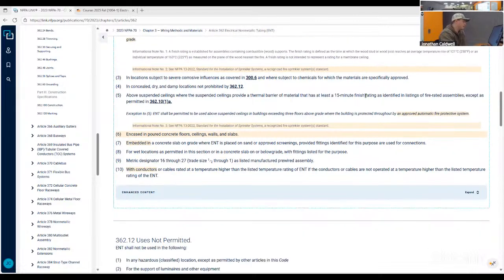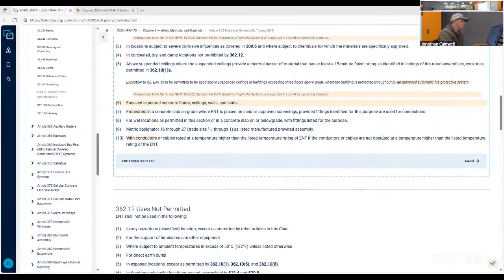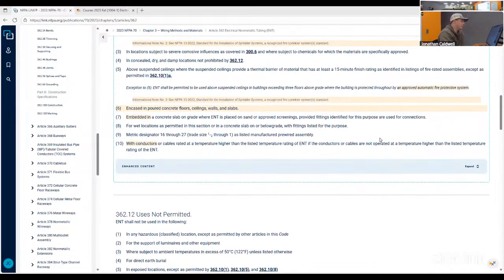Encased in poured concrete floors, ceilings, walls, and slabs, embedded in a concrete slab on grade where ENT is placed on sand or approved screenings, provided fittings identified for this purpose are used for these connections. For wet locations as permitted. Trade size 1/2 inch through 1 inch, as a listed manufactured prewired assembly. That would go for like a car harness. Some of them are ENT. And then with conductors or cables rated at a temperature higher than the listed temperature rating of ENT, the conductors or cables are not operated at a temperature higher than the listed temperature rating of ENT.